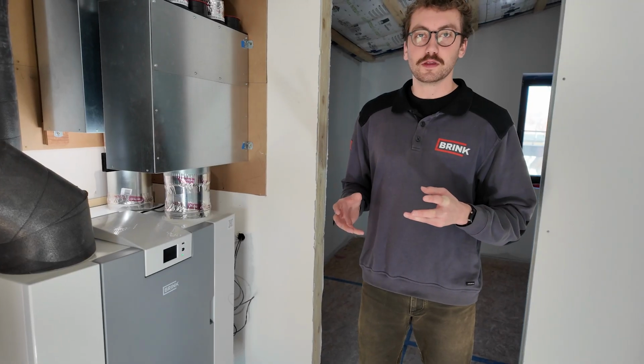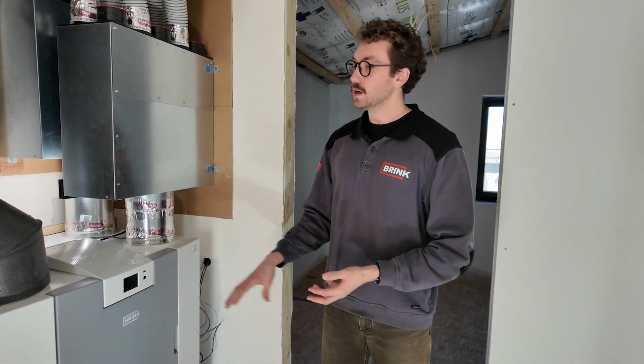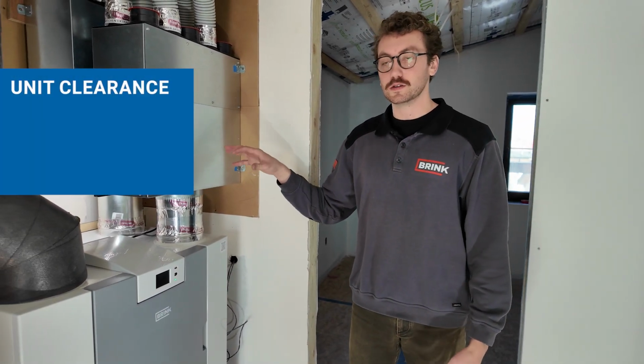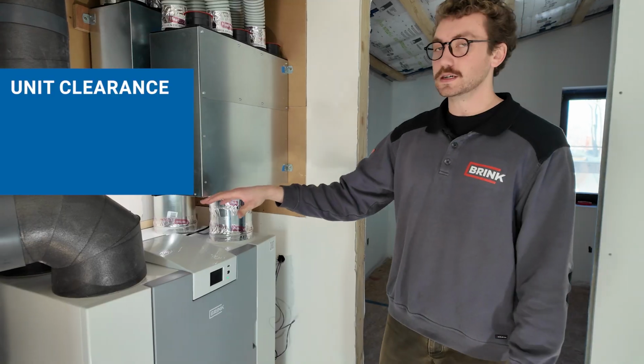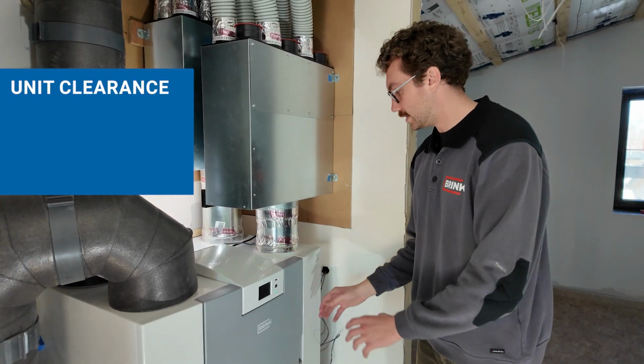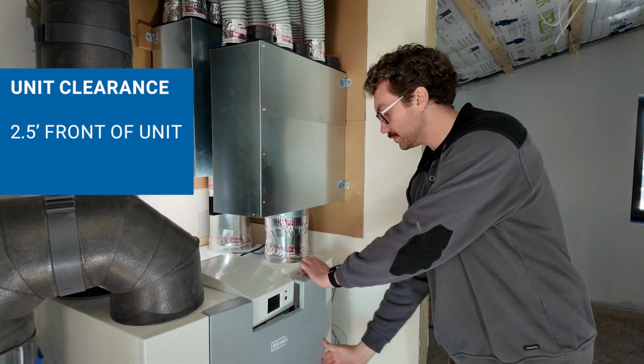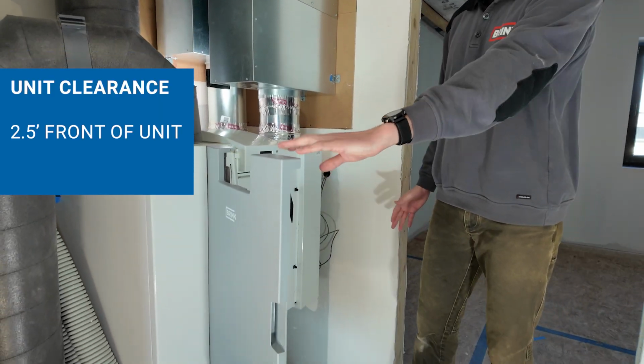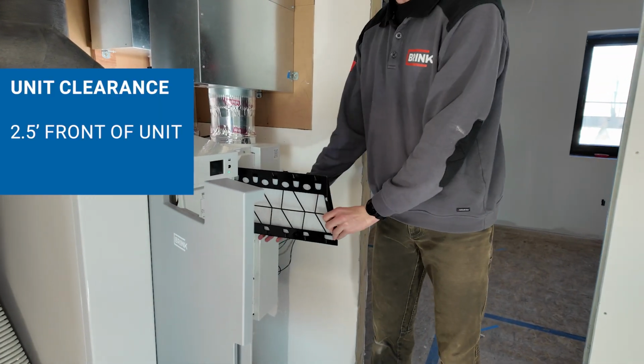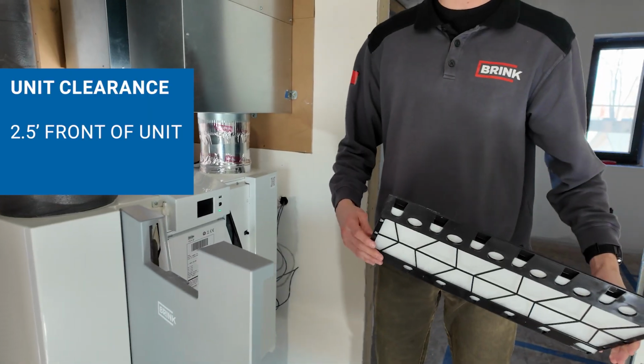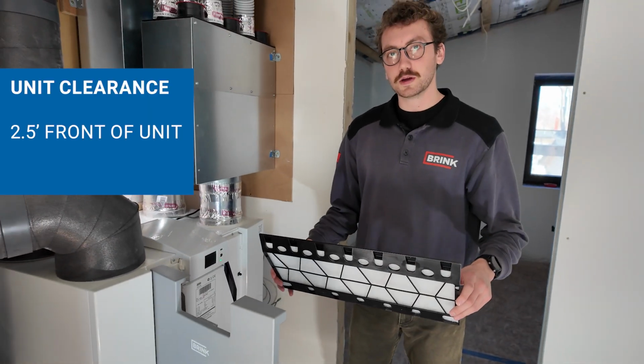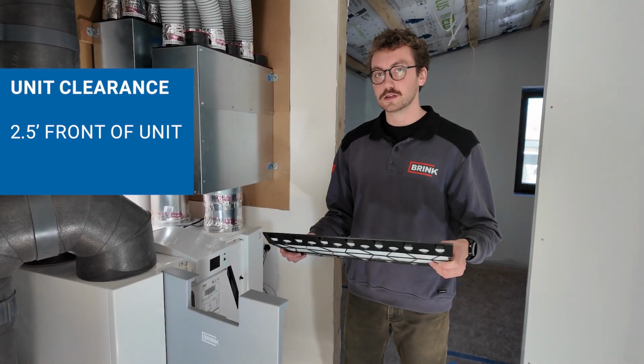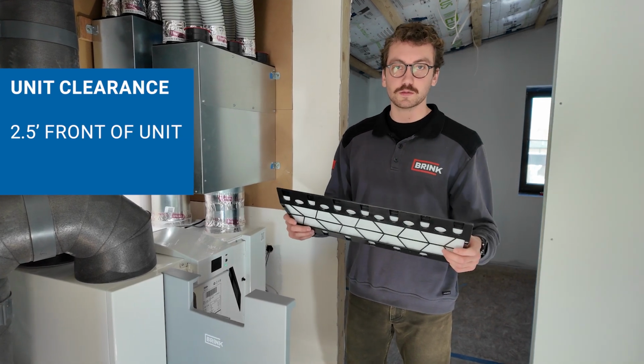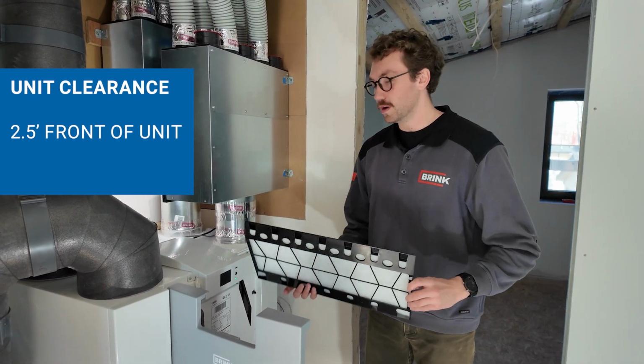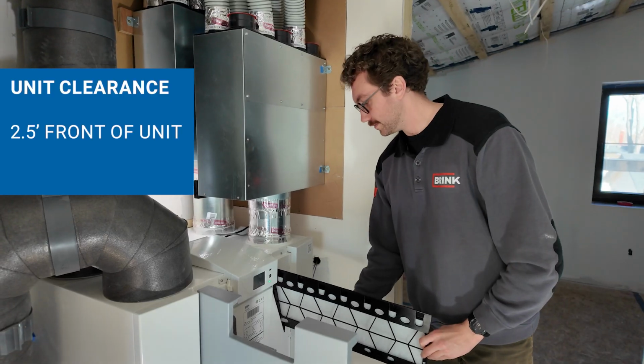Another one of the really important things when installing the unit and inspecting it before commissioning is making sure that we have enough space around the unit to both change the filters and access the electronics on top of the board. So we open up the door and make sure that the door has room to open and that we have room to access the filters. Obviously in this room we've got plenty of space, but some spaces might be a little bit tighter. Changing the filters every 3 months to 6 months is a very important thing, and we want to be able to have easy access to that.